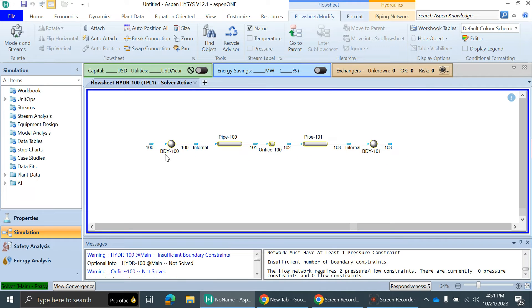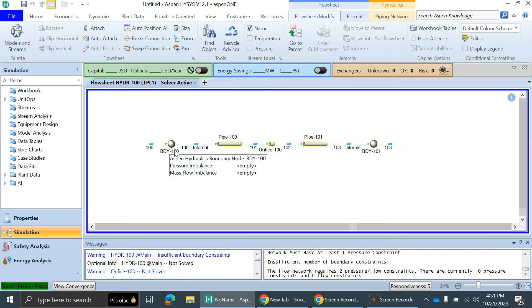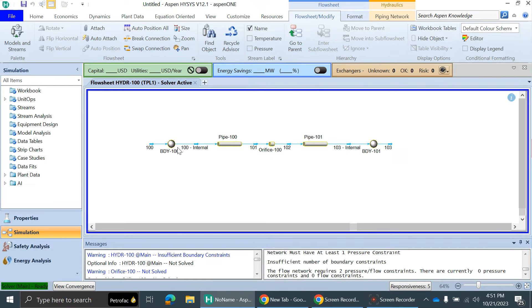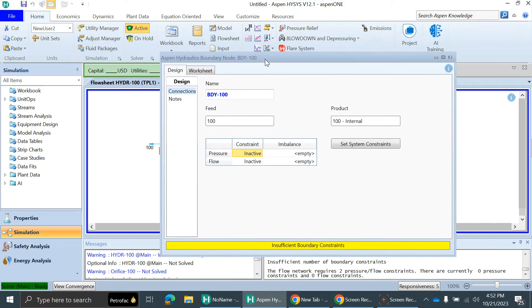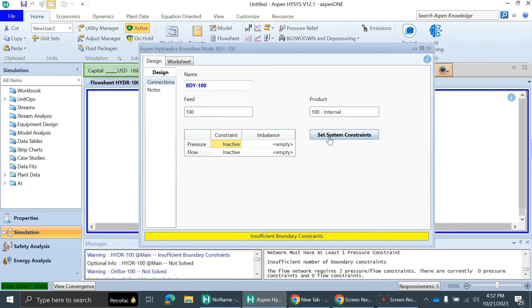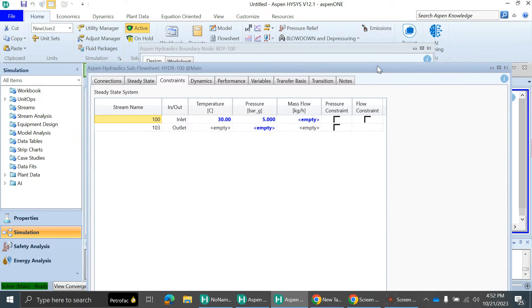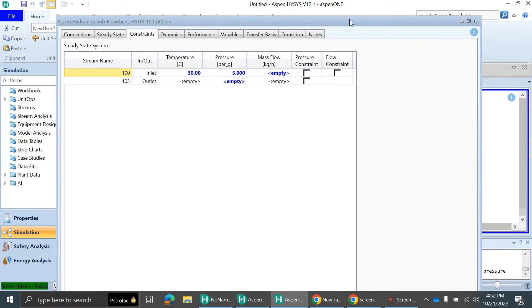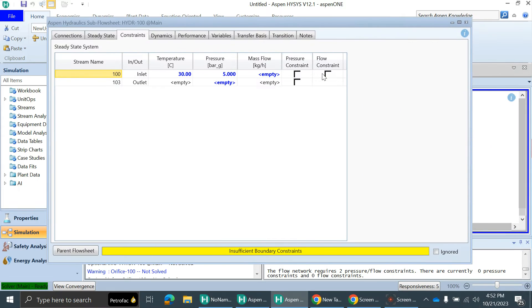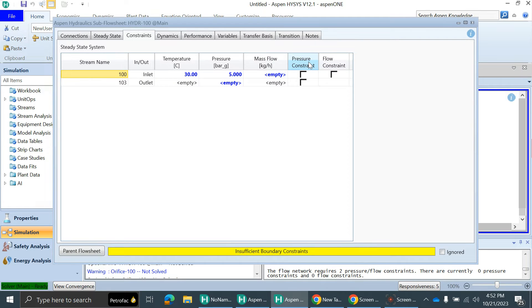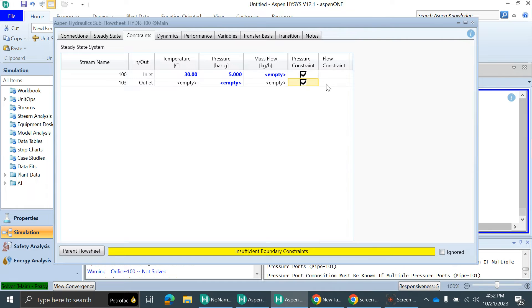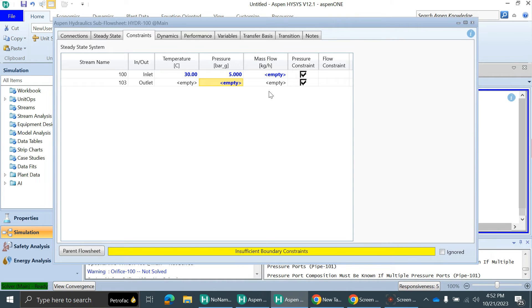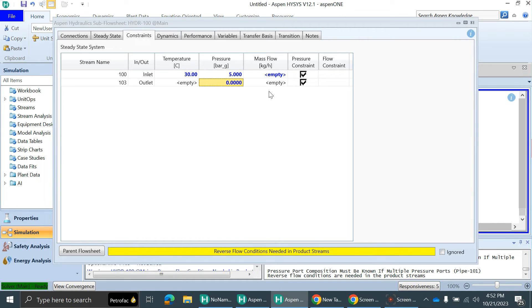After doing that, we need to add some boundary conditions. This is the inlet and this is the product. Once you click on boundary conditions, there is one option: Set System Constraint. If you click on that, you can see you can have a pressure constraint or flow constraint. Let's say we have pressure conditions at inlet and outlet of the orifice. If you click on that, the flow constraint will disappear automatically. You can only define two constraints. Let's say we have a pressure at the outlet of the orifice. Let's say this pipe is open to atmosphere: 0 bar gauge.